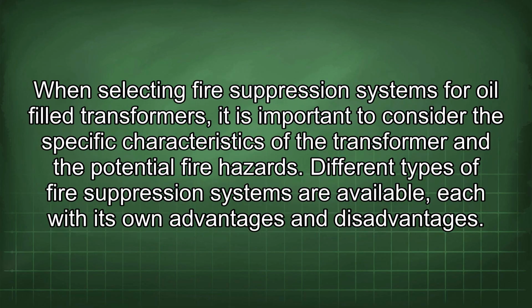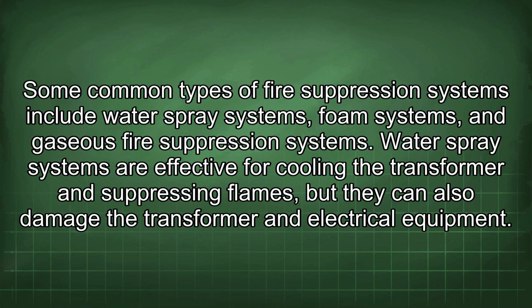When selecting fire suppression systems for oil-filled transformers, it is important to consider the specific characteristics of the transformer and the potential fire hazards. Different types of fire suppression systems are available, each with its own advantages and disadvantages. Some common types of fire suppression systems include water spray systems, foam systems, and gaseous fire suppression systems.